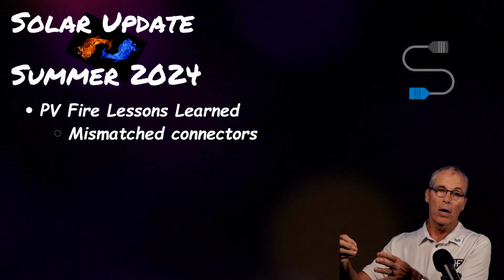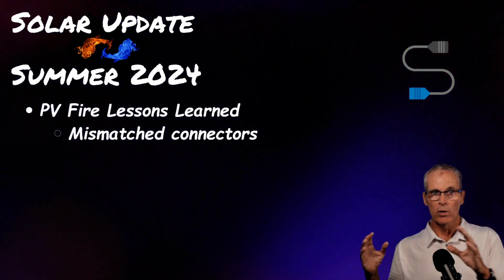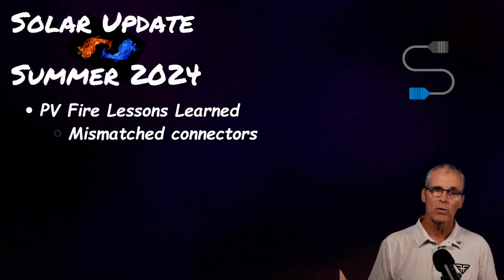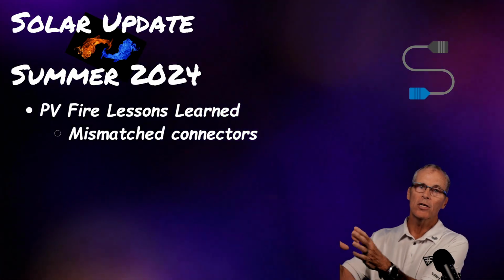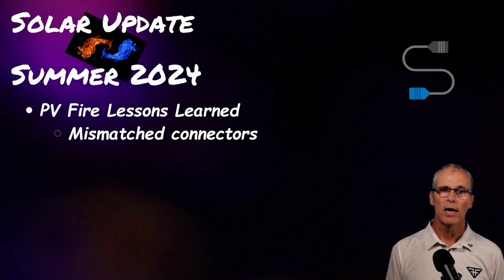The first one to lead to an overheating or a fire, or become loose, we'll start looking at the ones in that area. And if we find any more in that area, we'll expand our search. But we really don't need to just go out and start looking for problems if they're not showing us problems. Once they tell us they're there, then we can start looking a little bit in that area. I think that's probably going to be a good approach for mismatched connectors.